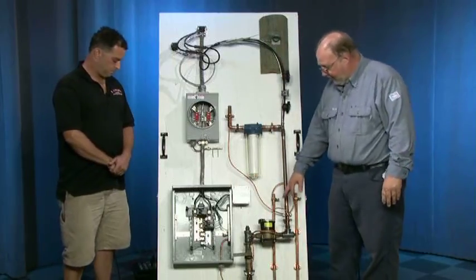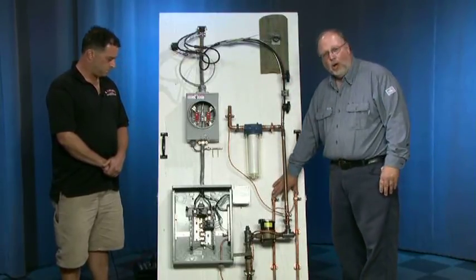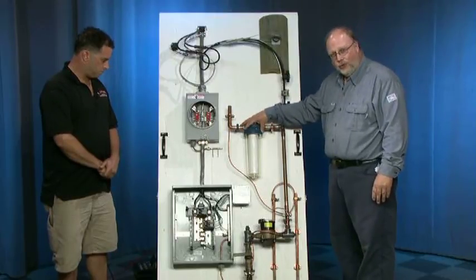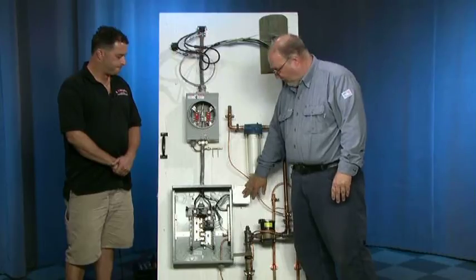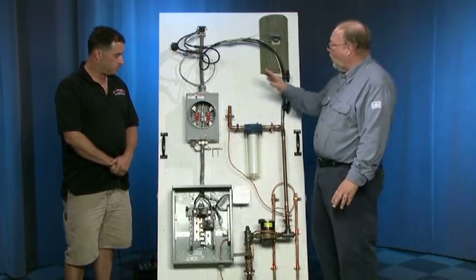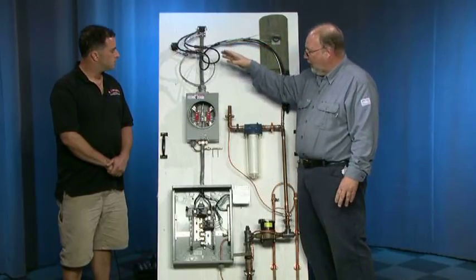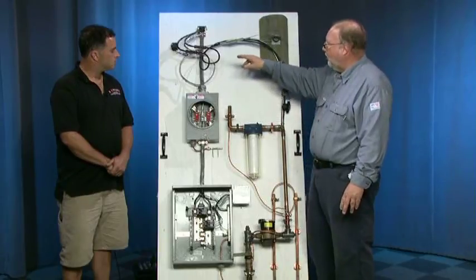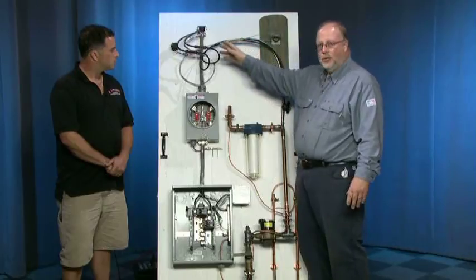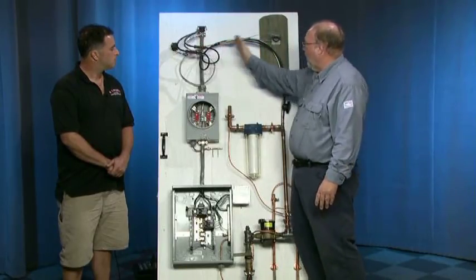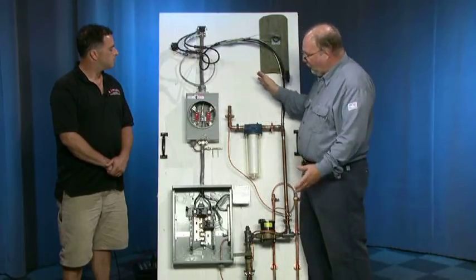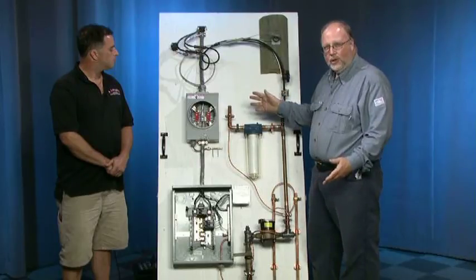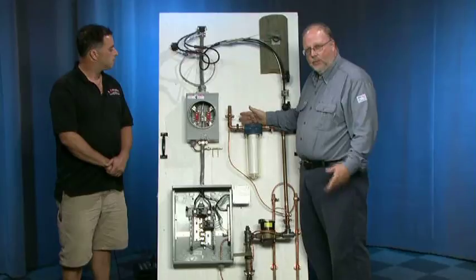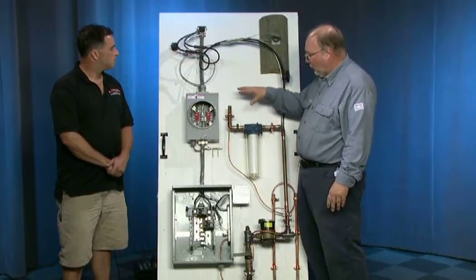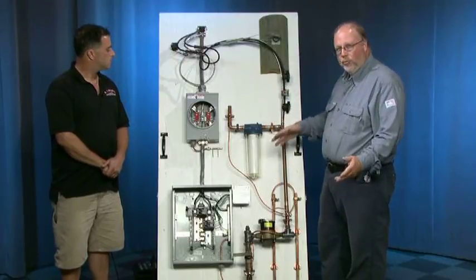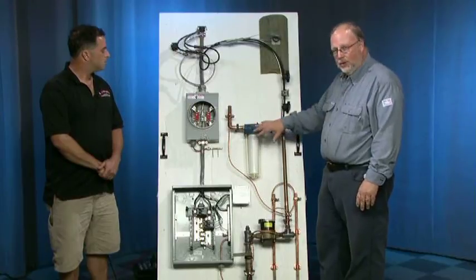And from the meter box, it goes to your service panel, which is located inside your house. And we've also added a water meter, a couple of ground rods, a water filtration system, and a surge protection system. The electric company only owns the wire from the pole to the house and the meter that goes in the meter box. The boundary line, also known as the demarcation point, are the connectors. From the connectors back to the pole we own, and we own the meter. Everything else you see here is owned by you, the homeowner, and is your responsibility for keeping in proper maintenance of good electrical condition and secured to the house. Rich is going to talk about some of the proper grounding rules that apply to this service.